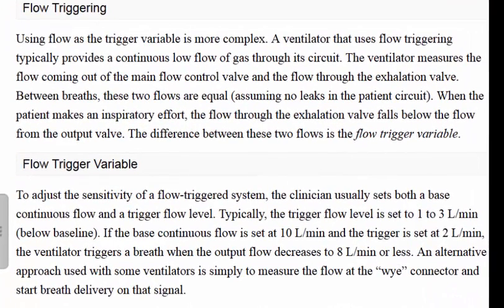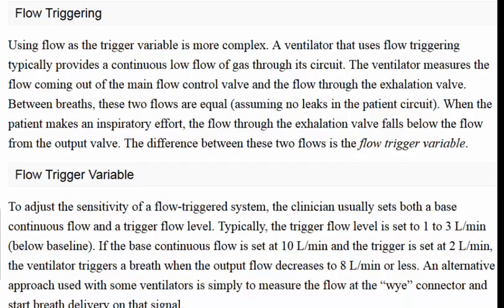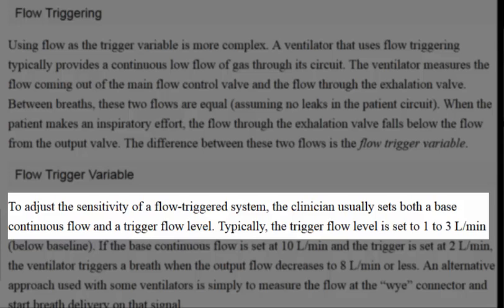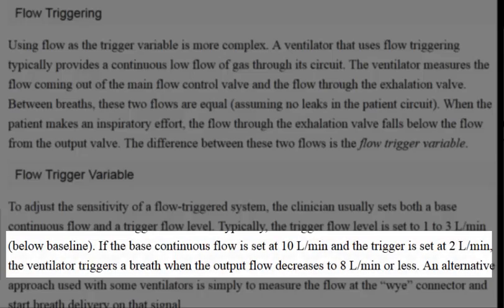Flow triggers are becoming more and more popular on machines simply because they are more sensitive to the patient's effort. They work a little differently than the pressure trigger. In flow triggering, the clinician usually sets both a base continuous flow and a trigger flow level. Typically, the trigger flow is set at one to three liters per minute below baseline. If the base flow is set at 10 L/min and the trigger is set at two, the ventilator triggers a breath when output flow decreases to eight liters per minute or less.